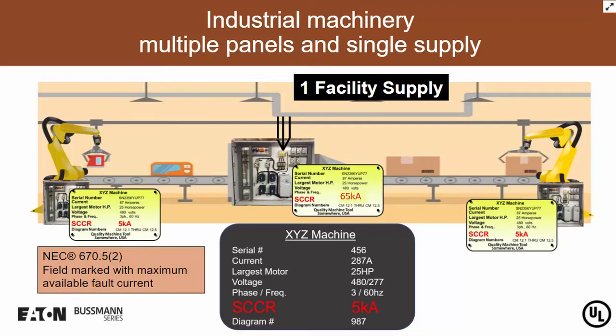So for example, if you had 50,000 amps available at the line terminals of the main panel, and you went through a study to determine at the line terminals of those sub-panels that the available fault current was 5,000 amps or less, then those sub-panels essentially are protected. And so now the entire machine takes on a short circuit current rating of 65 kA, because the sub-panels are protected, and the main panel, which has a rating of 65 kA, is greater than the available fault current of 50 kA at its line terminals.